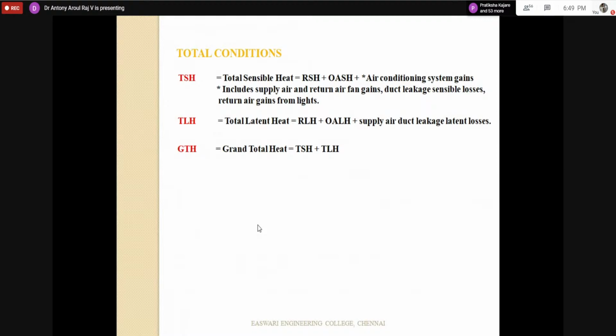What is the total load? The total sensible load is the total sensible heat, which is room sensible heat plus outdoor air sensible heat plus the system gains. Air conditioning system gains means sensible system heat gains, which include supply air, return air, and duct air leakage, all the sensible components. And what is the total latent heat? The total latent heat is room latent heat plus outdoor air latent heat.